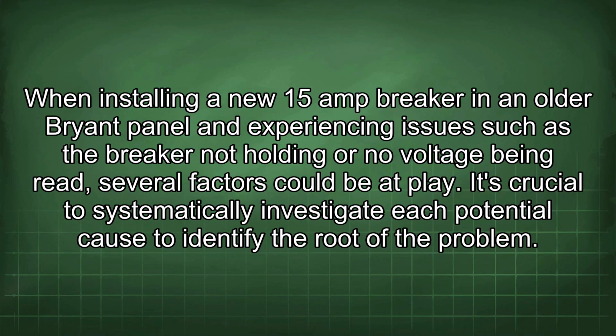When installing a new 15-amp breaker in an older Bryant panel and experiencing issues such as the breaker not holding or no voltage being read, several factors could be at play. It's crucial to systematically investigate each potential cause to identify the root of the problem.